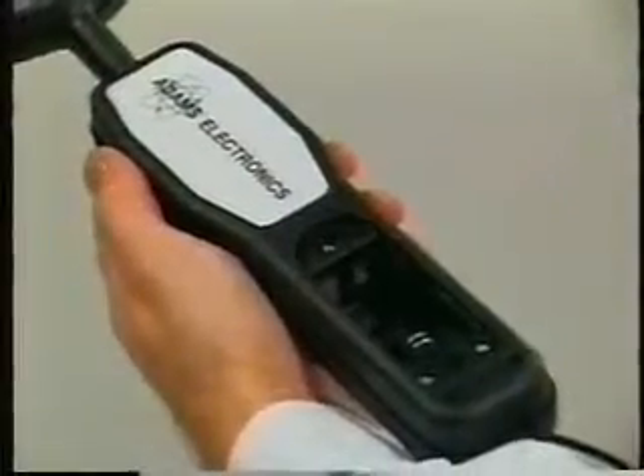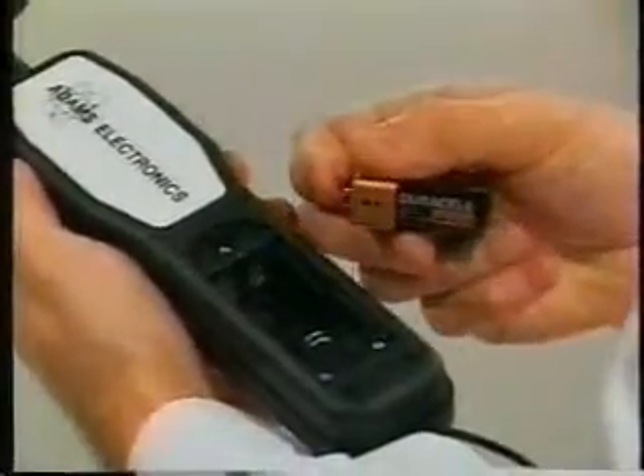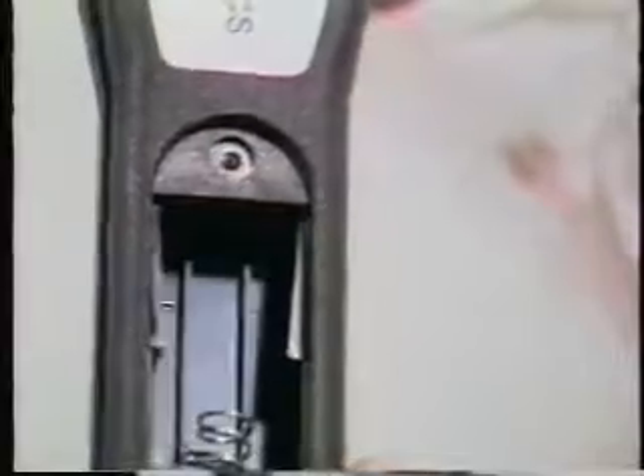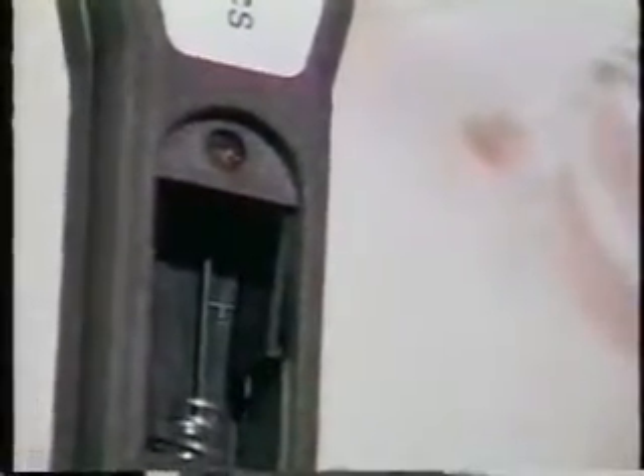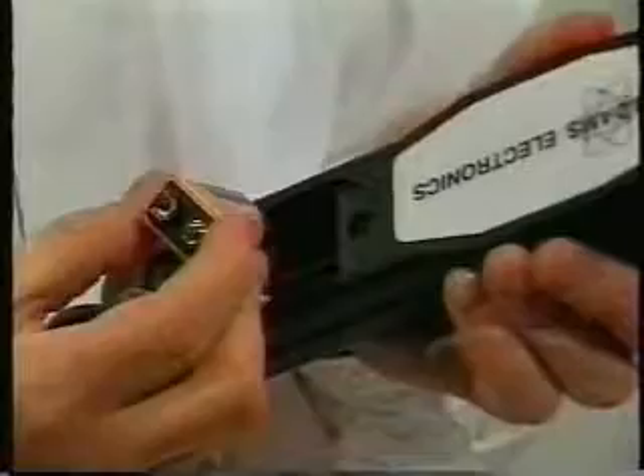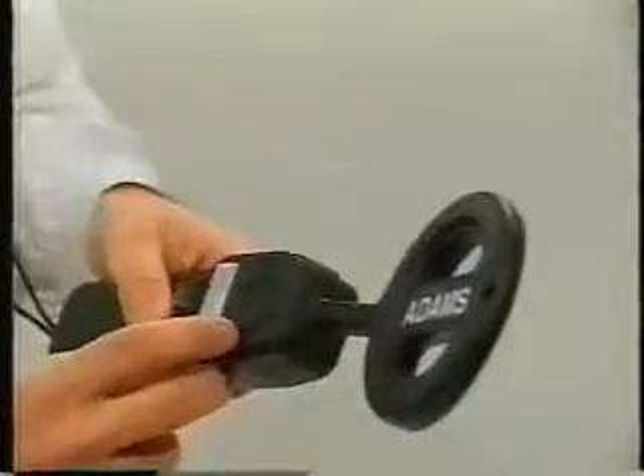To reinstall the battery, return it to the compartment, making sure it is put in correctly. You can see the positive and negative copper contacts in the empty battery compartment. Push back on the spring and snap the battery back into position. If the battery does not snap in correctly, turn it over and snap it back into place. Replace the compartment cover and refasten the retaining screw. The detector is now ready to be calibrated for use.